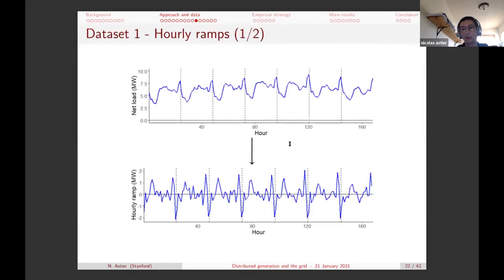The second object we look at in this work is hourly ramps. It's a more recent focus in the power system literature, which is driven by things we are observing in California. So far it's mostly a system-wide issue, the idea of the California duck curve. Once you install a lot of solar PV, you get a lot of production during the day, but at sunset production decreases and load stays high. So you need to ramp up a lot of gas turbines to make up for that, and you have to make sure that your electricity system actually enables that.